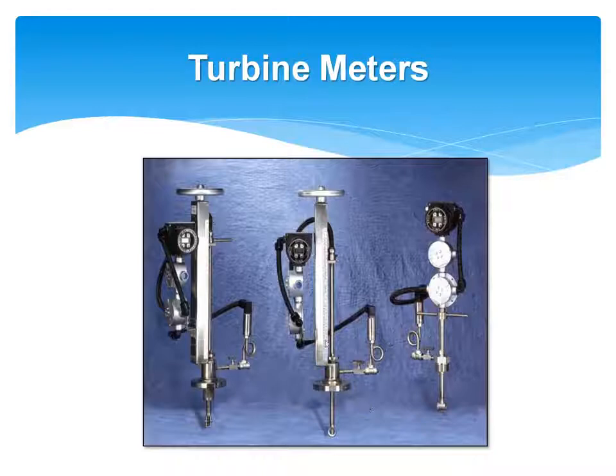Where a turbine meter actually does a good job is in situations, getting back to these retrofit applications, where you can't shut the steam lines down and you want to be able to hot tap an existing meter in, but you can't change the pipe size, so you can't move the velocity. A lot of these applications have very low flow steam, and a turbine meter might be a good selection for that type of installation.